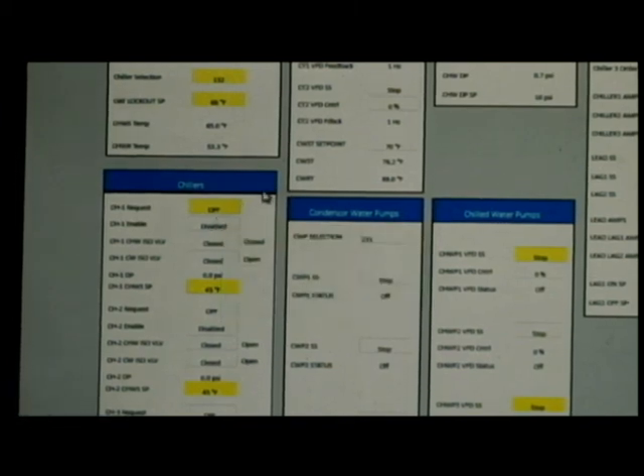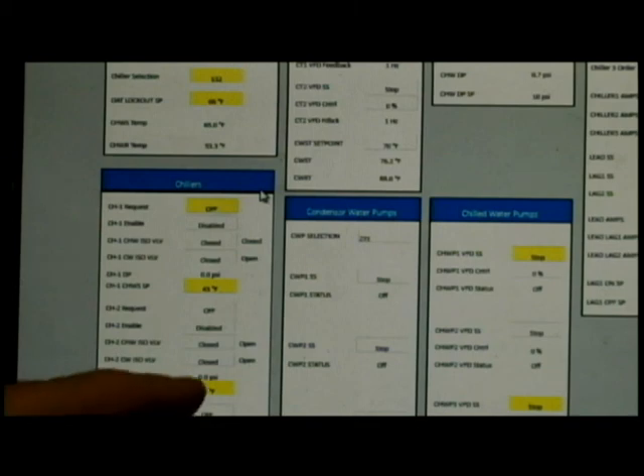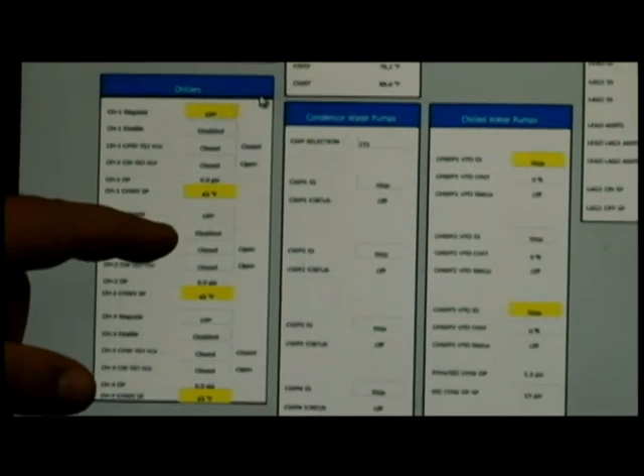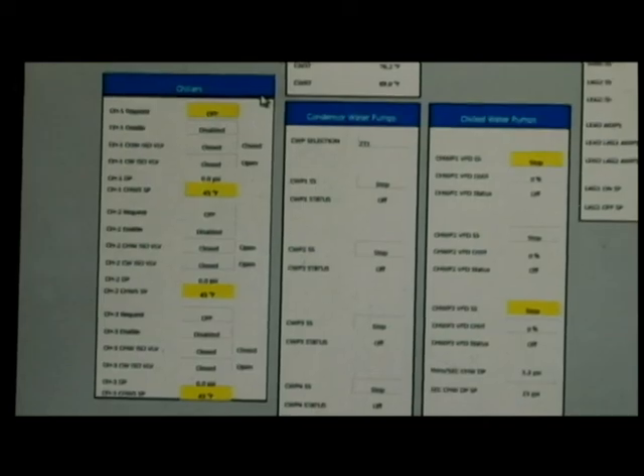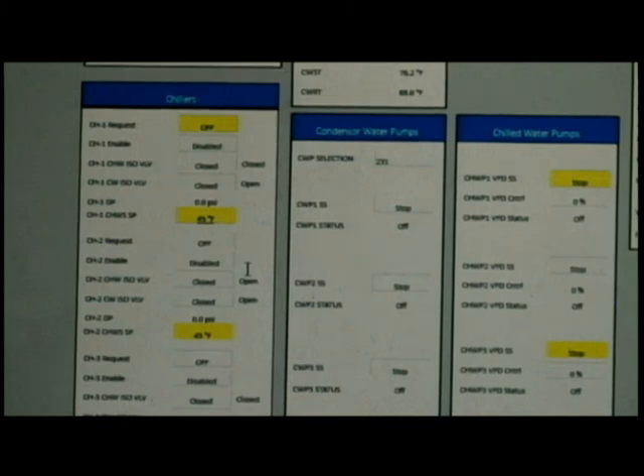Last thing you'll notice in here is we have some boxes that are yellow and some that are just white around the information there, the point. The yellow is what we use to indicate that a point is in manual control. So if the point is in manual, like I said, then it stays in that setting no matter what code we write in there, because it ignores any programming when it's in manual. If that yellow box goes away, so we can say like this set point here for the chiller one, if we put that to auto, the yellow box goes away, and that just tells us that point is in auto.